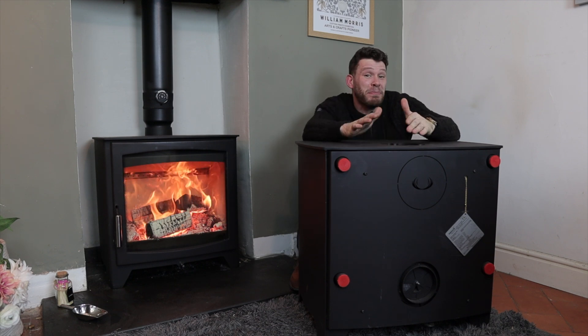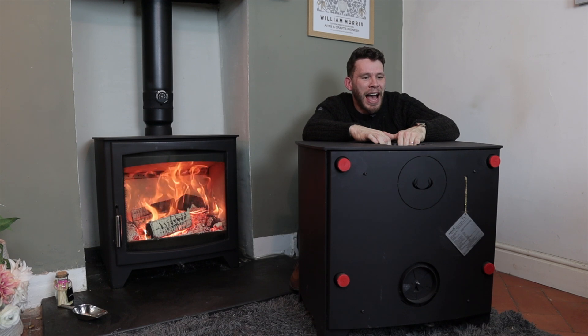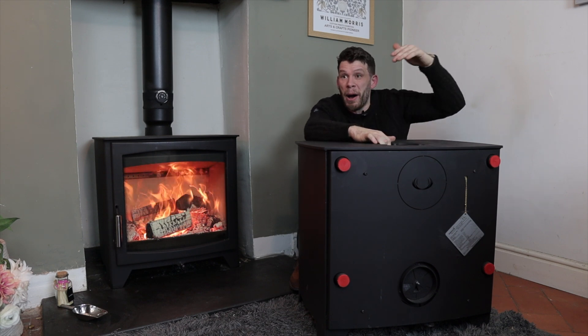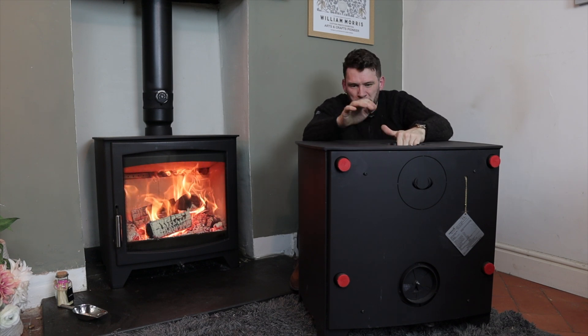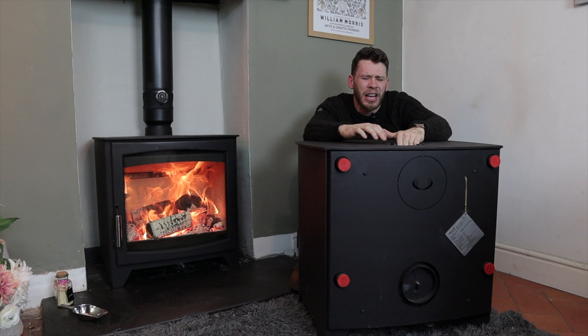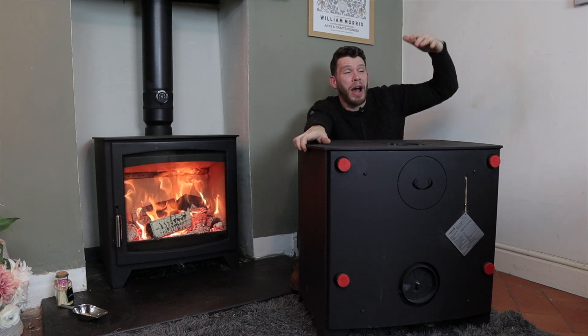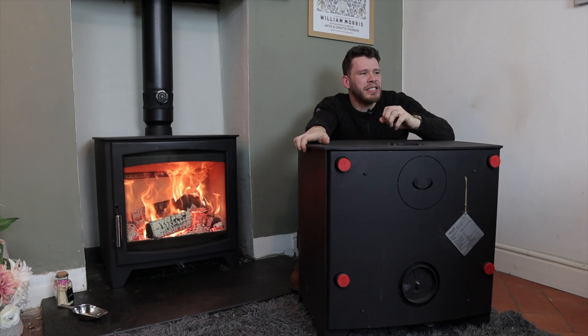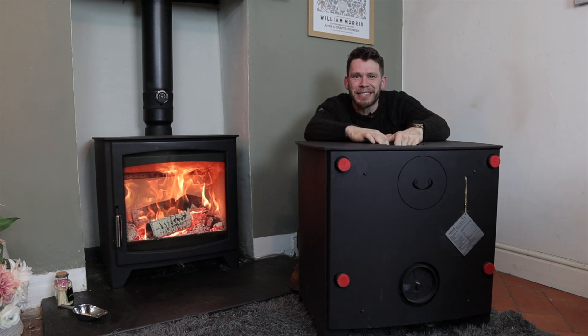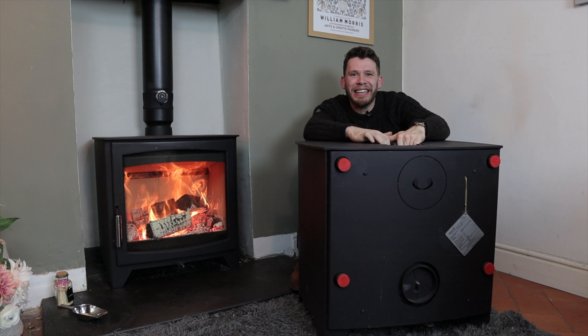The reason I've made a specific video about it is partly because boiler stoves are a rarity, but also since these new regulations have come in, these have become incredibly difficult to get to pass modern regulations. This boiler stove runs at something like 0.06% CO emissions, which is incredible. They've managed to get something as big, powerful, and utilitarian-focused as this to tick all these modern government boxes, which is really impressive. I wanted to draw attention to that because I feared these could be lost from the industry — but it appears they won't be, which is fantastic.